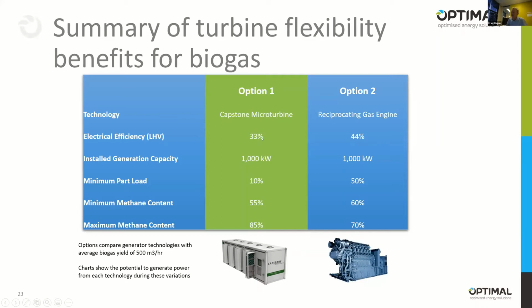So on the face of it, our open cycle efficiency is 33%. The nameplate efficiency of these gas engines looks really high at 44%, with the same electrical capacity output. But here's an interesting factor: our micro turbine package can run all the way down to 10% of its installed capacity. A gas engine will run to 50% of its installed capacity, and then it's off.